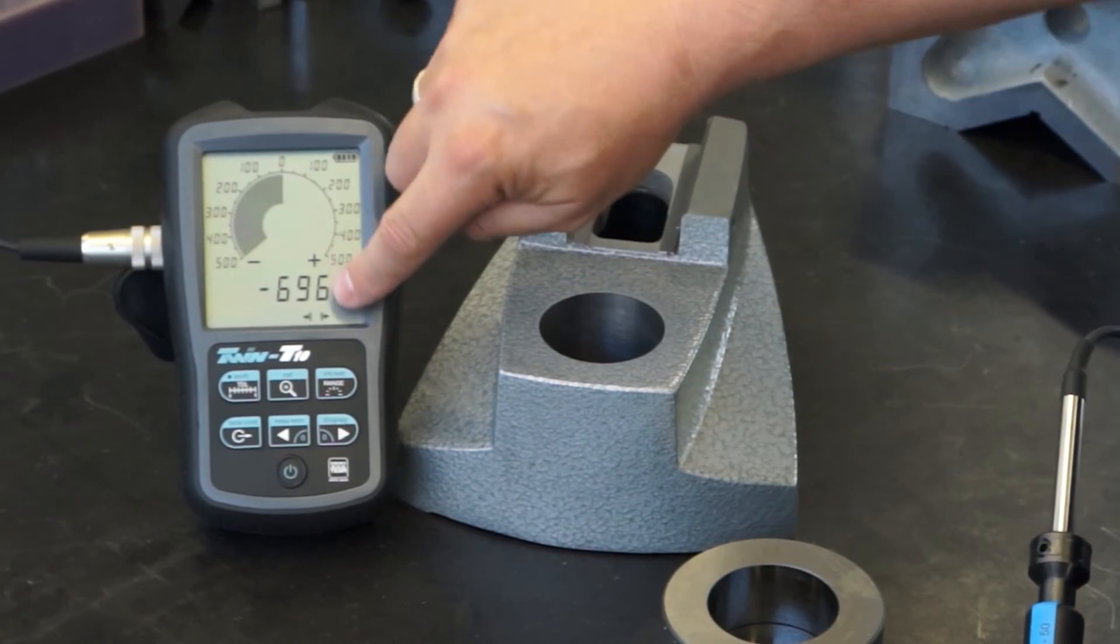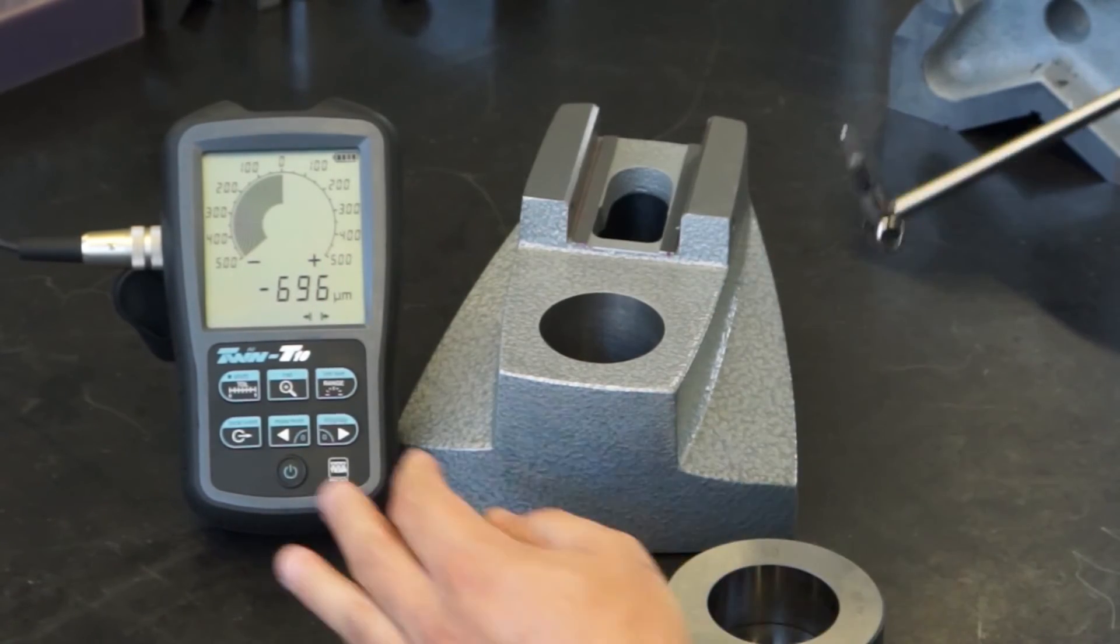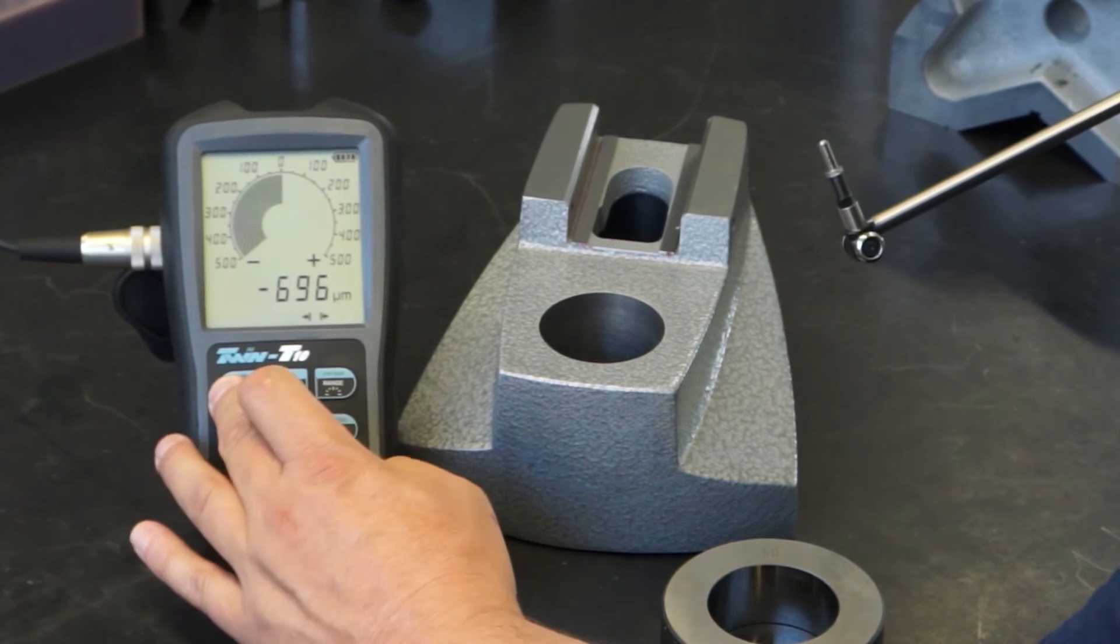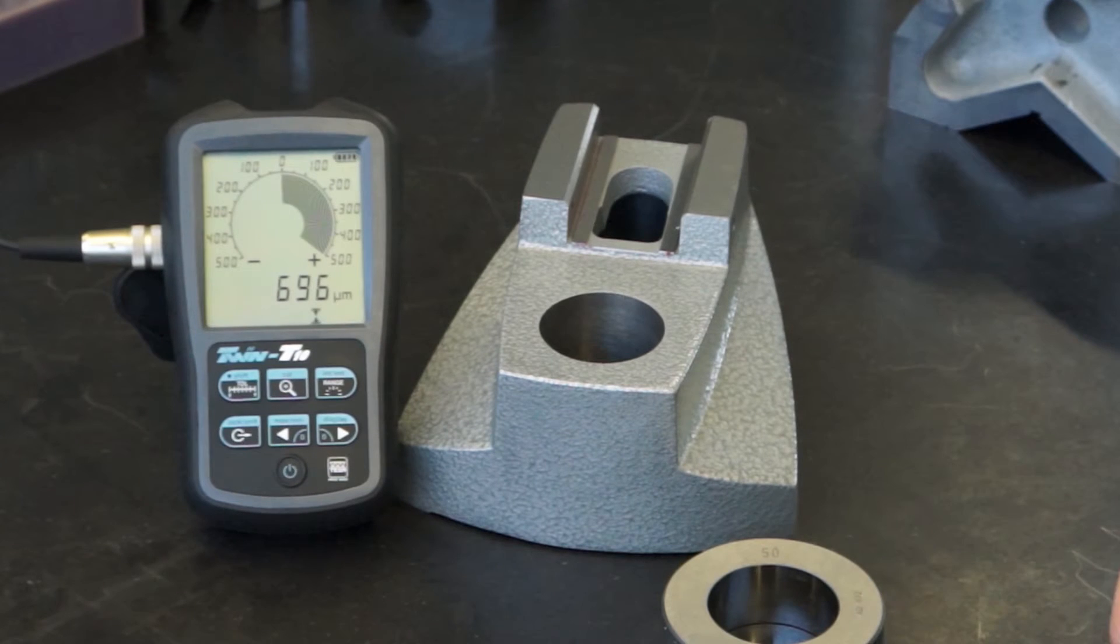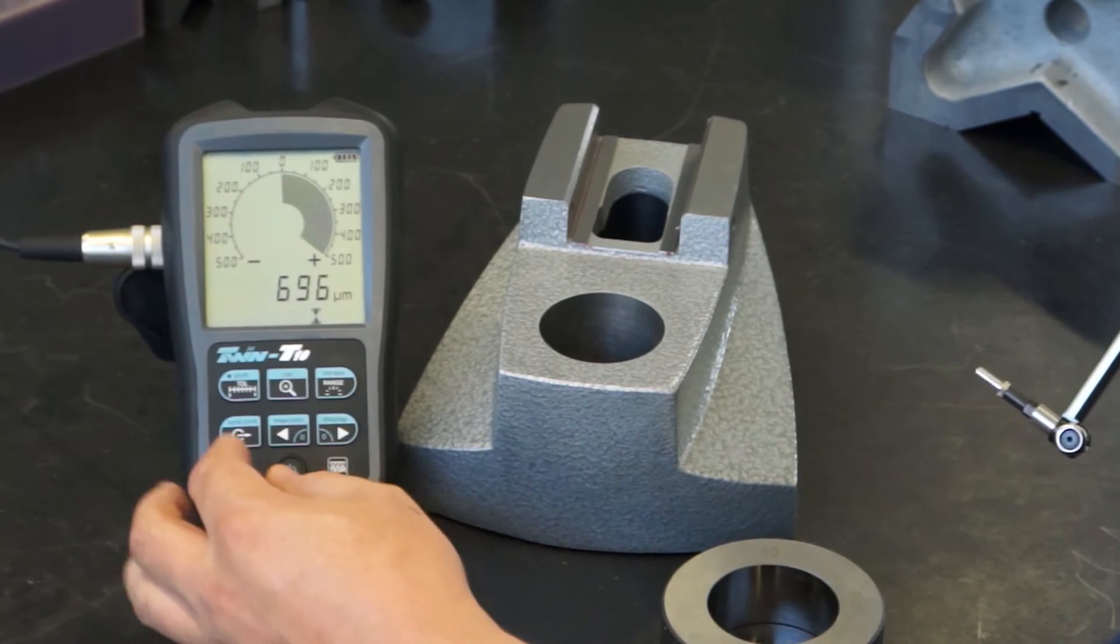The display shows that the TWIN T10 is currently in plus-A external measurement mode, and we need to change it to minus-A internal measurement mode. Press the shift and internal external keys until you see the display switched to minus-A measurement mode.